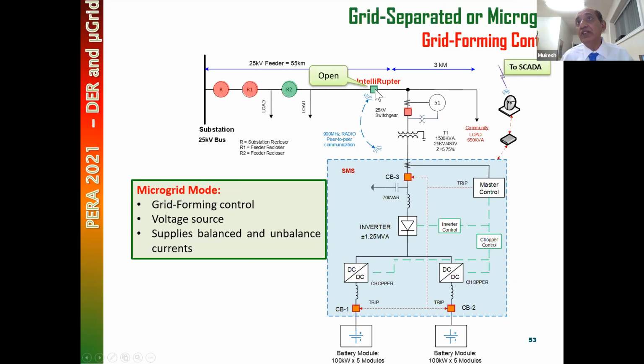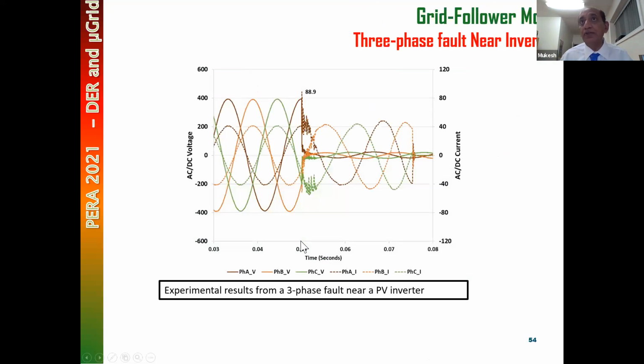When this is open and this battery is operating like a microgrid here, supplying this load, the control system is switched to grid forming mode. That means the control system of this inverter will be in grid forming mode. It will be controlling the frequency and voltage, as well as supplying unbalanced current. That means it will supply the single phase load, the unbalanced load. It is able to supply unbalanced load too.